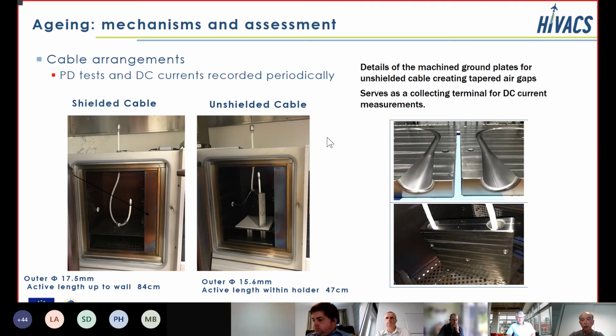And for the unshielded cable, we machined ground plates, which are shown here, in order to have a distribution of distance between the cable and the surface, to explore different distances for the PD occurrence. And the plate also serves as connecting terminal for the DC current. So that was done on two PTFE insulated cables with 2.7 millimeter thick insulation.